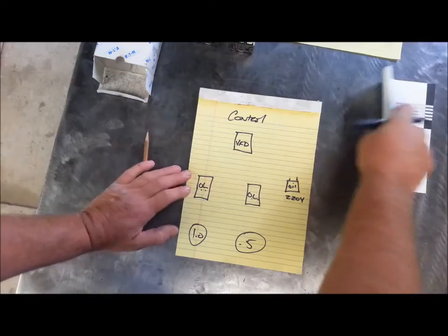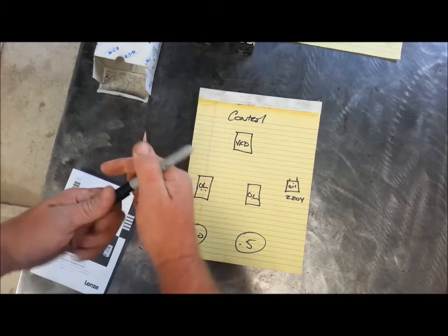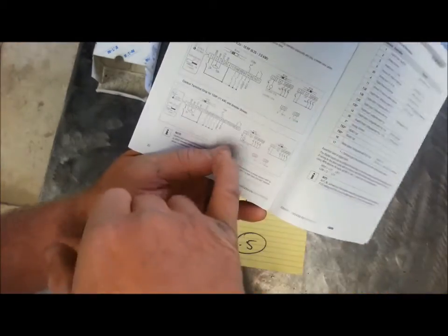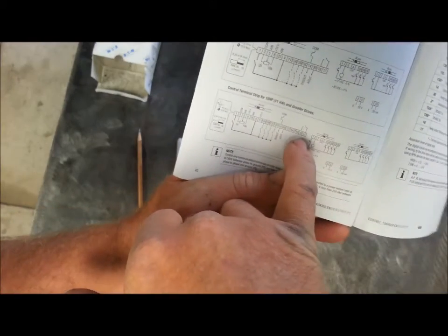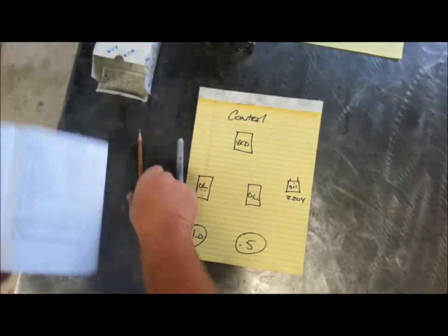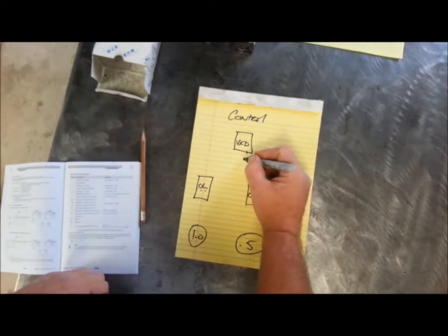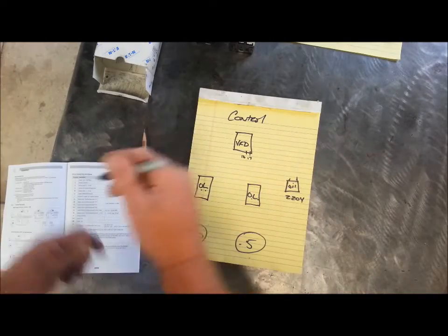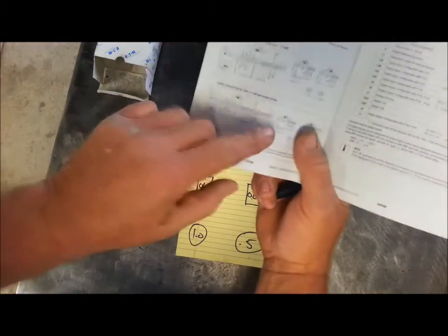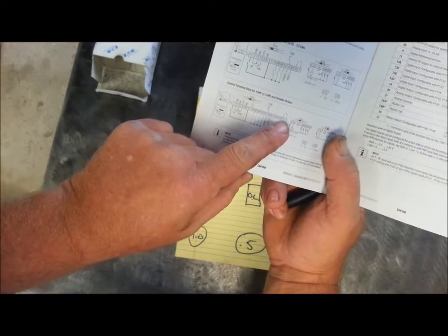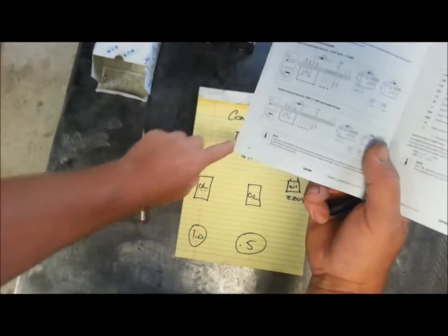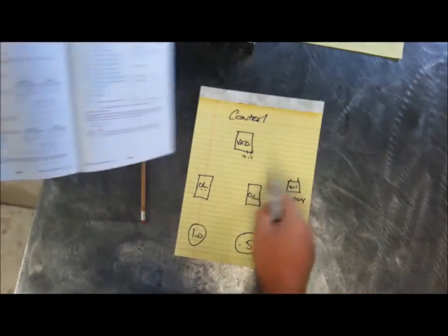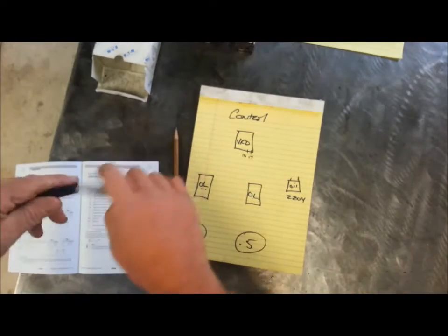Now what we're going to do is use the programmable switch gear. You need to bear with me a second while I find it here in the book. Programmable switch gear is on 16 and 17 on the terminal strip. And we can make this switchgear do whatever we want it to do via the programming. We're going to close this switch when the VFD is given a run command, and this switchgear is going to operate the oiler.